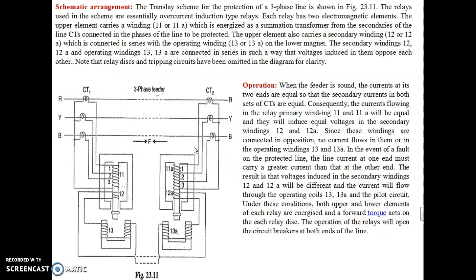Okay, see here the schematic arrangement. This is the schematic arrangement of the Translay relay. Here in the Translay relay we are considering a balanced voltage scheme with the addition of a directional feature. Okay, you know how a directional relay works and all the concept. So this is a balanced voltage scheme with directional features. Okay, and here an induction disc type relay is used at each end of the line. The secondary windings of the relays are interconnected in opposition, as a balanced voltage system, by the pilot wires.